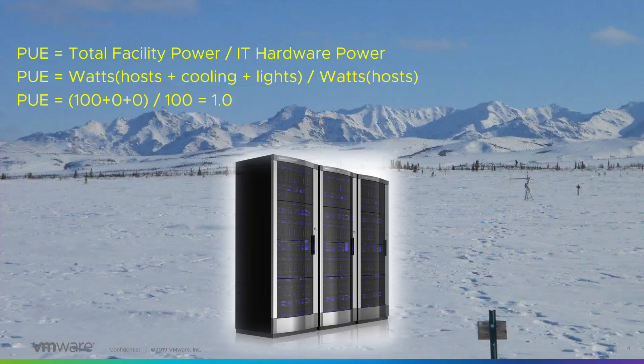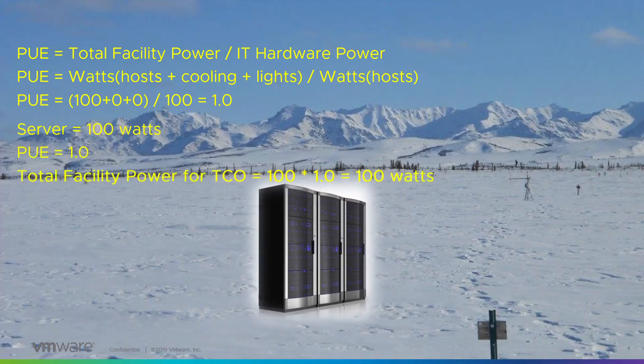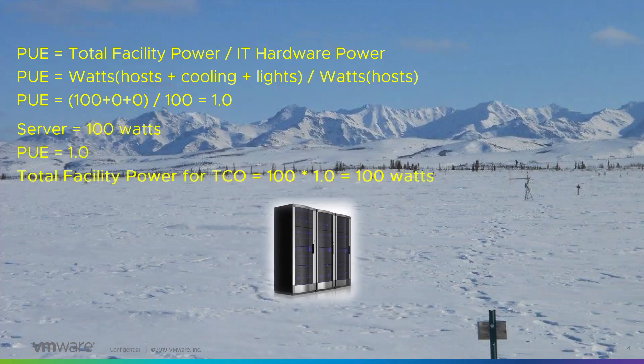Looking at our example, we now have 100 plus 0 plus 0 divided by 100, which gives us a PUE factor of 1.0 — which, by the way, is the lowest a PUE factor can be. So if we know our server takes 100 watts and our PUE factor is 1, then we can calculate our total facility power for our TCO at 100 watts. And that is how we do PUE.